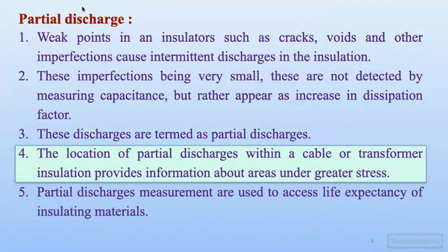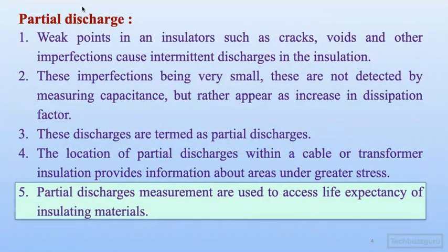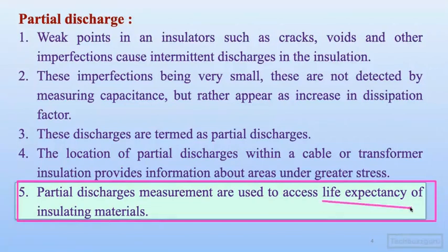Okay, so we come to the next point. Partial discharge measurements are used to assess the life expectancy of insulators or insulating materials. So this is very, very important: partial discharges are used to determine the life expectancy. I mean, how long the insulator is going to stay in service.